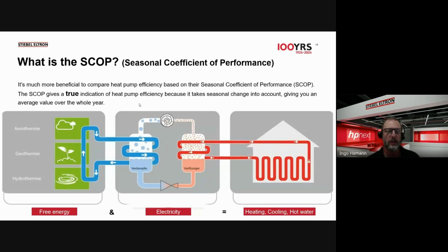So at the moment we have in Johannesburg here 20 to 25 degrees. And if I produce a hot water flow towards the buffer tank of 50, 55, or 60 degrees, the COP might be 4.5 or 5. If it's 5 degrees outside, the COP is only 3.0 or 2.0, depending on the machine. But it's changing every second. The COP is basically changing.